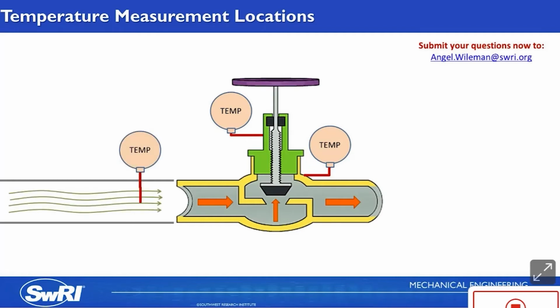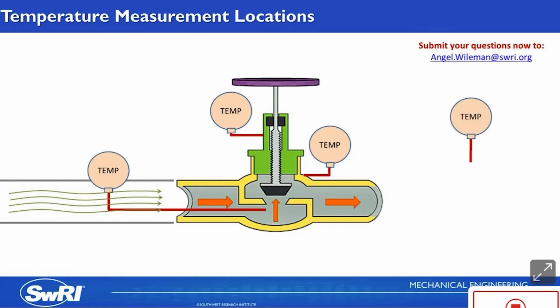The third thermocouple is not required by 624 or 641, but it is required for the ISO standards, and it must be installed in the flow path. Now, technically, the thermocouple I have shown on the screen now is in the flow path, but it's best practice to extend the thermocouple probe all the way into the internals of the valve as close as possible to the closure member. It's also good practice to have a room temperature measurement, getting your ambient temperature, and this is a required measurement for some of the specific end user specs.